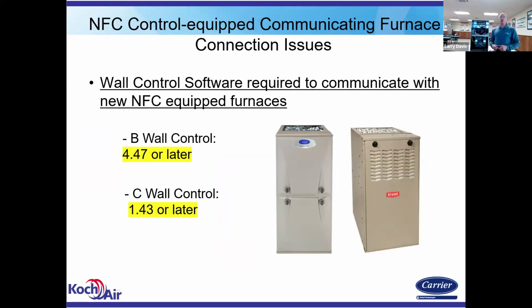A question came up earlier on the communicating furnaces with the new boards. It has to be the B or C control. The O controls will not work. The B control has to be at a 4.47 or later. The C control has to be at a 1.43 or later. What you'll find is if you go out and plug up and you put your system in and you fire it up, the wall control will not find the furnace. And then it's done. It'll go into demo mode.